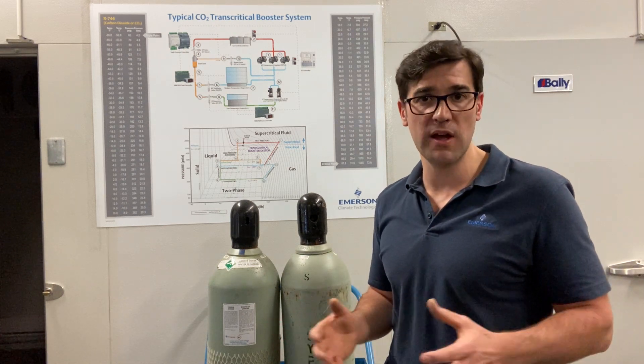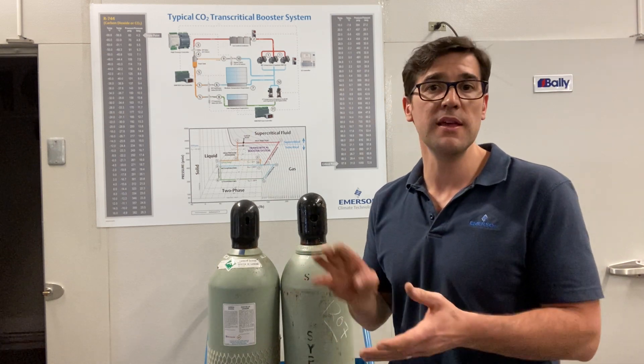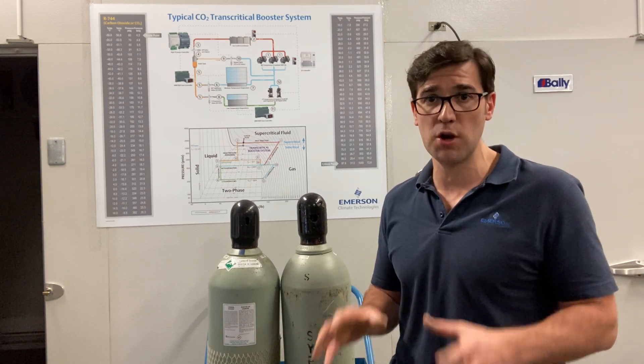How much vapor do you add? Well, I hear different numbers from different manufacturers. It could be 100 PSIG, it could be 125 PSIG, could be 145 PSIG or 10 bar — but what you need to make sure is that the whole system is above the triple point.